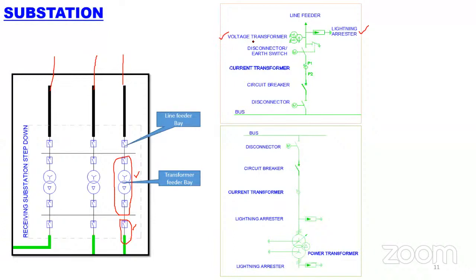What is a voltage transformer? It is called an instrument transformer. The reason is, when you receive the transmission line, either the control system or the human operator must know what voltage we are receiving. So the control system will operate or protect the system based on this voltage measurement, and the operator will understand what voltage we are receiving. Not only the voltage, it also helps to monitor the energy as well as the power in the network. It means the delivery of power and the energy for export or import from the network.